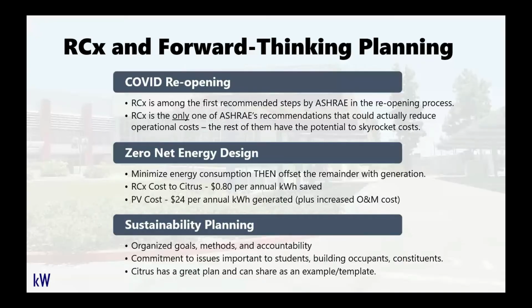And specifically, my first item here in terms of COVID reopening, as I mentioned, in my opinion, RCX is one of the very first things you should do when looking at the pathway to reopening buildings. It's also one of the first steps that ASHRAE recommends in their publicly available information about reopening. And in ASHRAE's entire list of recommendations, which includes increased filtration, increased air change rates, and possible additional purification, it is literally the only one of their recommendations that could actually reduce your operational costs and have an actual payback, as opposed to the other recommendations, which, while important to maintaining occupant comfort, are also perfectly capable of skyrocketing your energy costs if they are not implemented in a way that is considerate of the entire system's operation as a whole.